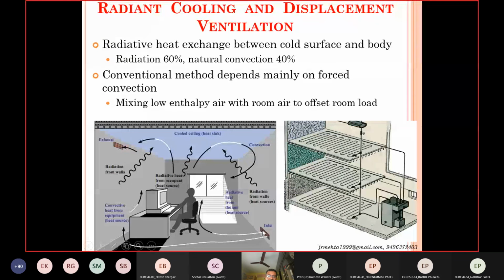Now, how you take care of the latent cooling is that you have to supply the air at a required low humidity level, a low value of humidity ratio. So the W is already low, so that it takes away moisture from the space and it is exhausted. This separate air that you are supplying is taking care of that. So you cannot have only a radiant cooling system. You have to combine it with dehumidification. Thank you, sir.